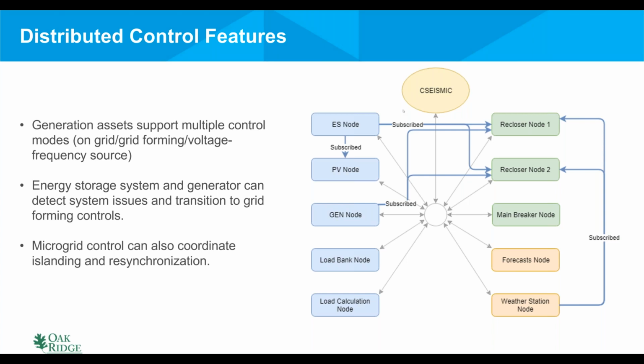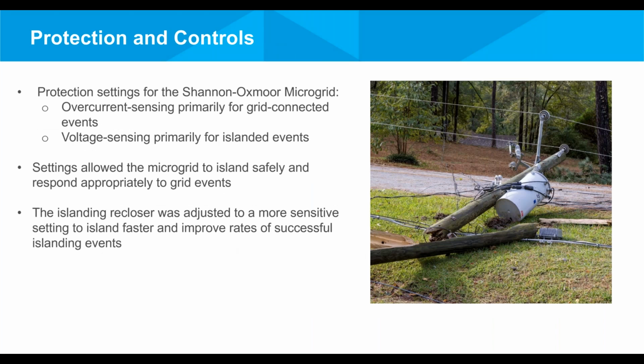So to do that, CSEISMIC is pointing to different nodes throughout the microgrid, such as the energy storage node, the PV node, and the generator node, and has to be able to conduct forecasting and get information from a weather station, and use all of that in the algorithm that helps it effectively dispatch the microgrid efficiently and reliably. Now, the CSEISMIC controller is used locally to control the microgrid, but beyond the microgrid, the smart homes and the microgrid are connected to the distribution system. There has to be the right protection scheme to ensure that the microgrid can operate effectively.